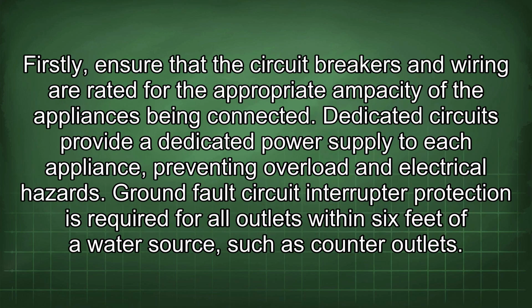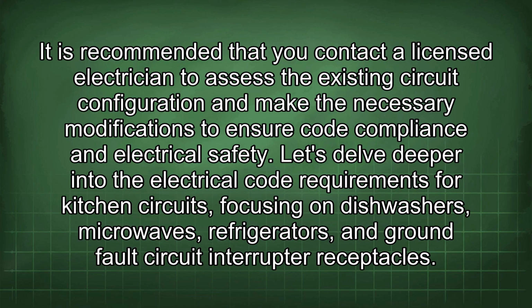Firstly, ensure that the circuit breakers and wiring are rated for the appropriate ampacity of the appliances being connected. Dedicated circuits provide a dedicated power supply to each appliance, preventing overload and electrical hazard. Ground fault circuit interrupter protection is required for all outlets within 6 feet of a water source, such as counter outlets. It is recommended that you contact a licensed electrician to assess the existing circuit configuration and make the necessary modifications to ensure code compliance and electrical safety.